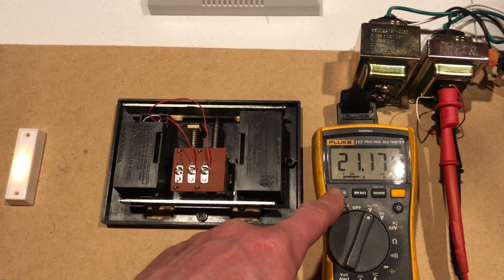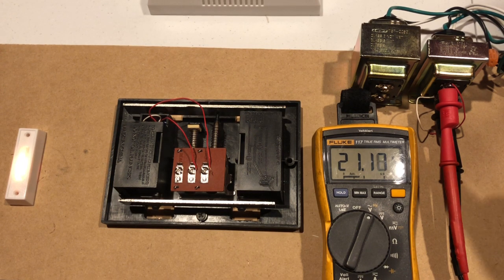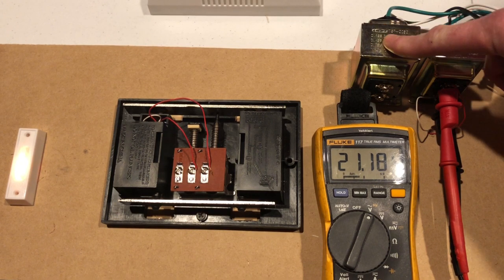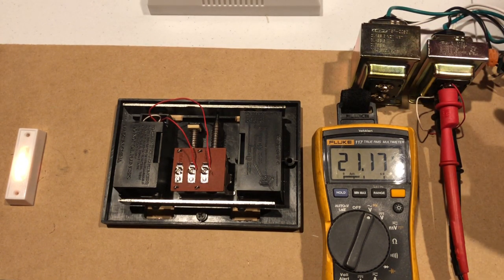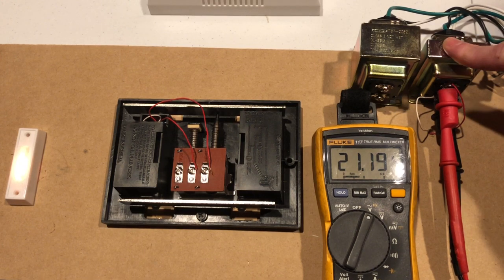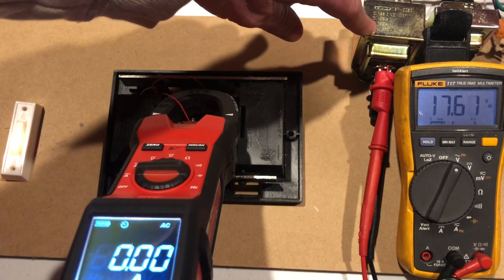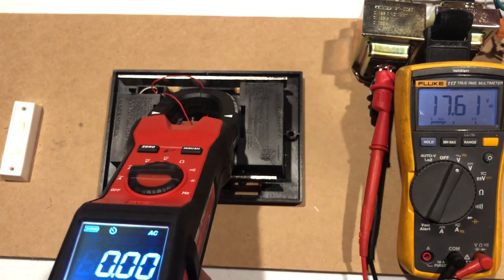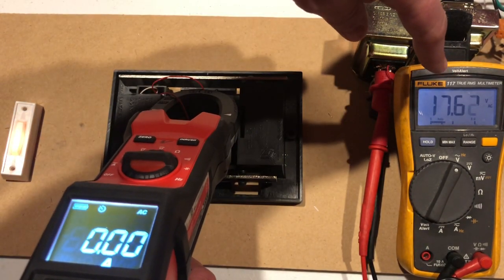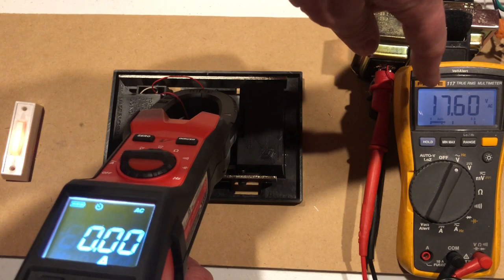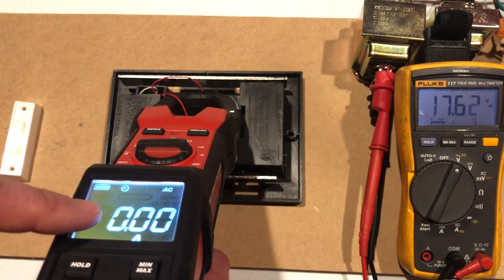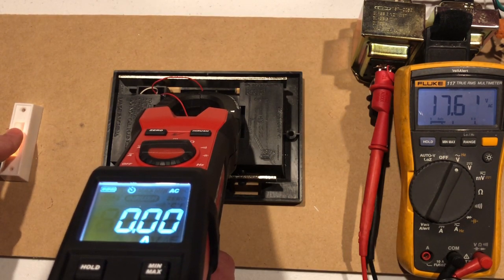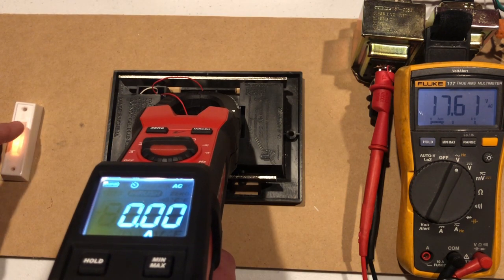So now let's test this on the 16 volt 30 VA transformer which is essentially three times the capacity of the 10 VA. We've switched over to the 16 volt 30 VA transformer and we're going to run these tests again. You can see that the 16 volt transformer is actually doing 17.6 volts and we've got zero amperage. Now I'm going to hit the button and pay attention to what both of these go to.